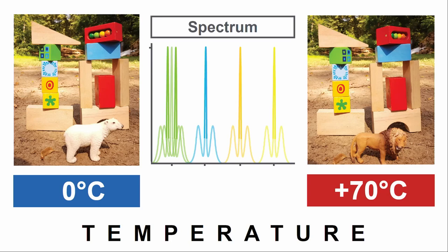But you can also make it more complicated or say, well, we had a second variable there, we had the time. So when we say we cool it down within 30 seconds from room temperature 20 degrees to 0 degrees, keep it there, and after 30 seconds again, it needs to be stabilized. And if it doesn't do it, it's a failure part. It might stabilize after 5 minutes, but we want to have it stabilized after 30 seconds.